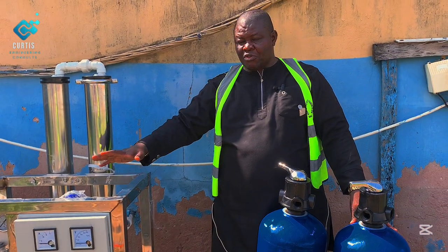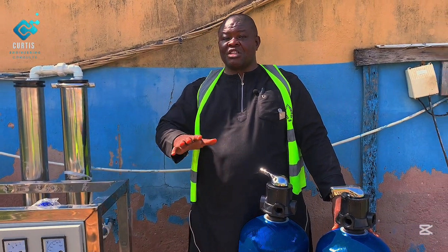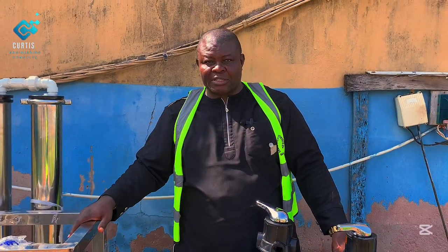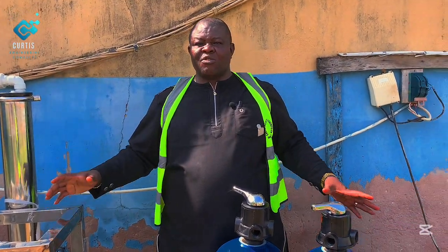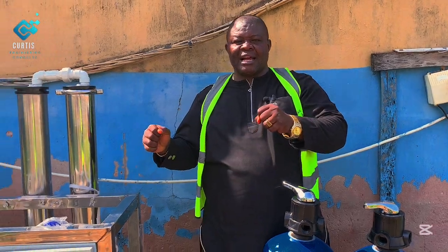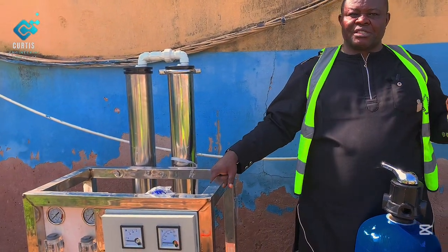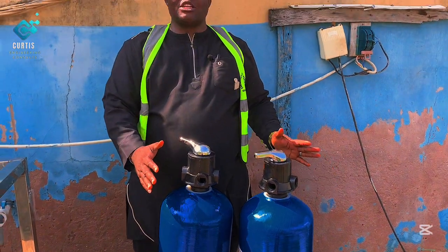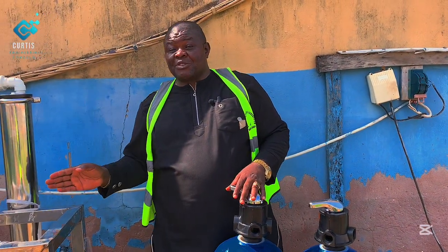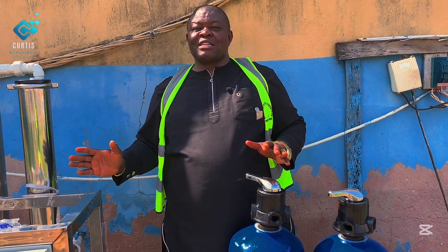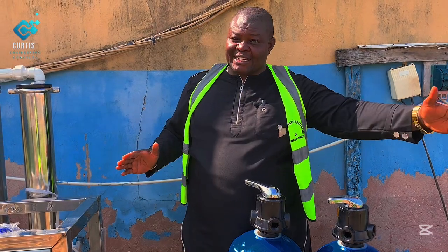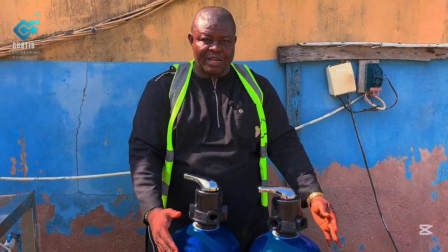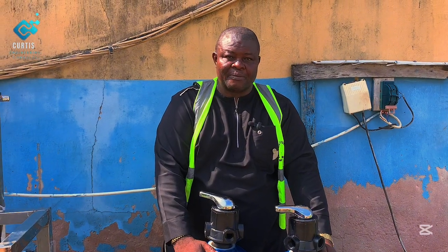Even if you use only the reverse osmosis, you can still treat the color, the taste, the odor, the physical properties, but it will be like overloading and giving a heavy job to the reverse osmosis. So when you do this pre-treatment, the water is already treated at this point before even entering the reverse osmosis. So the reverse osmosis lifespan is elongated by introducing the pre-treatment system. That is why we're introducing it.